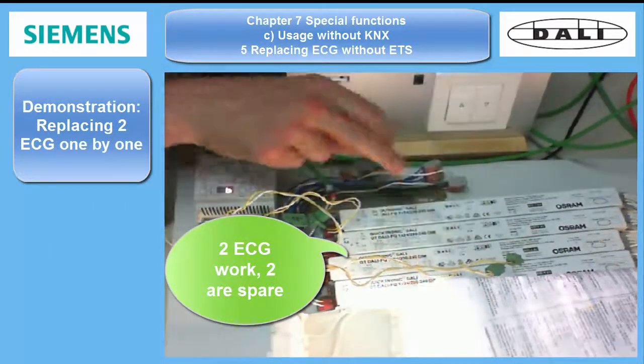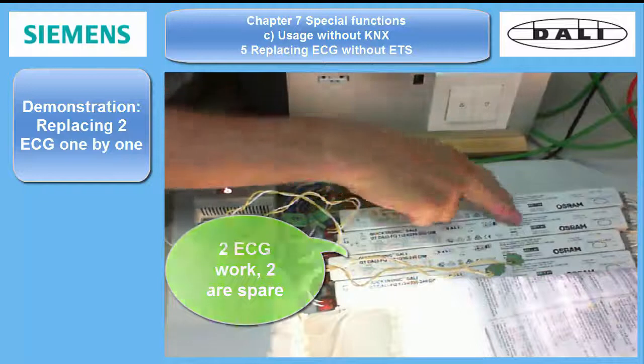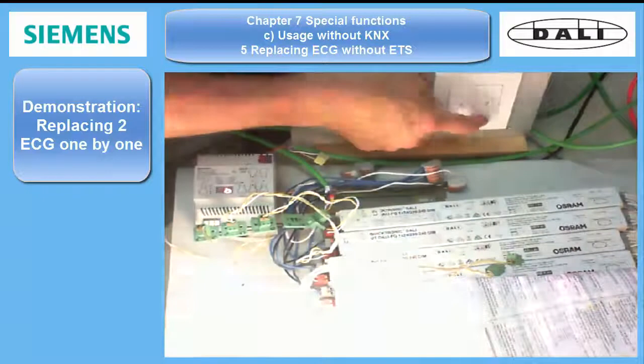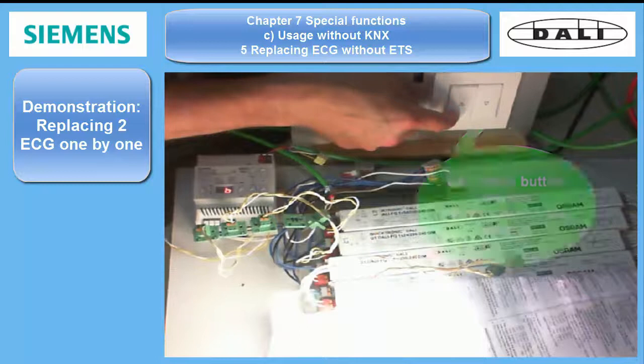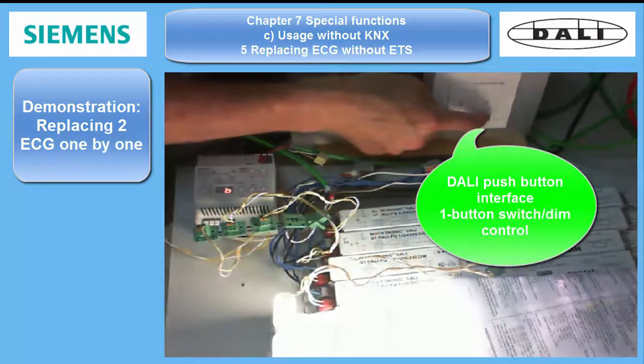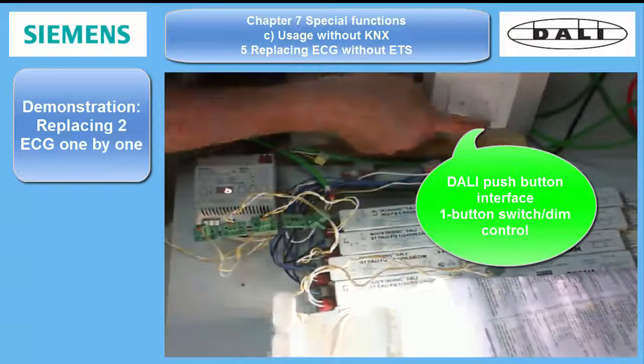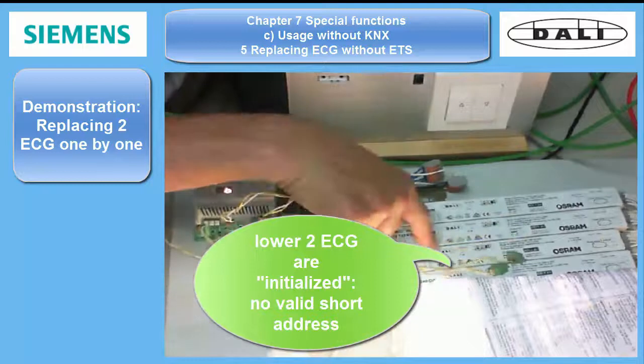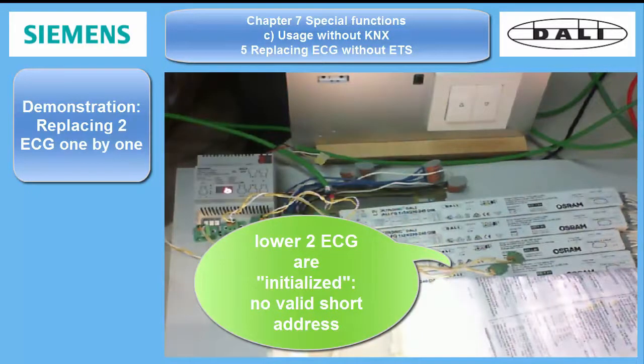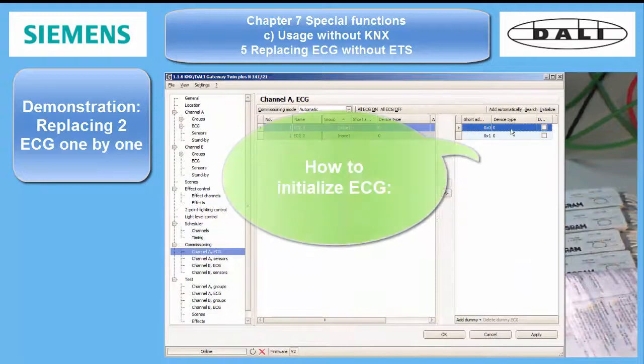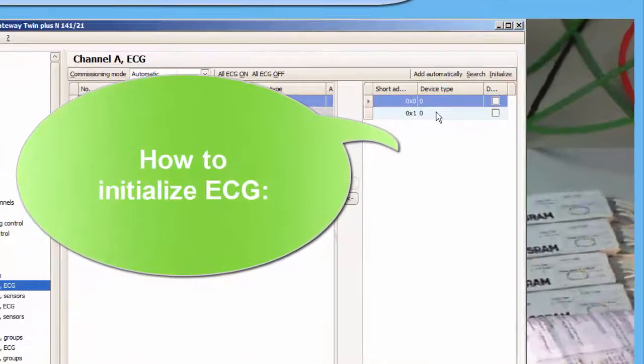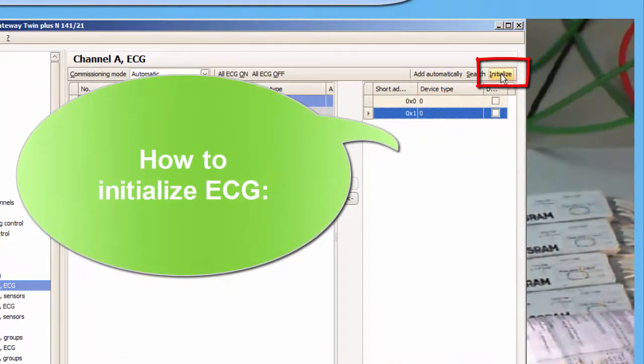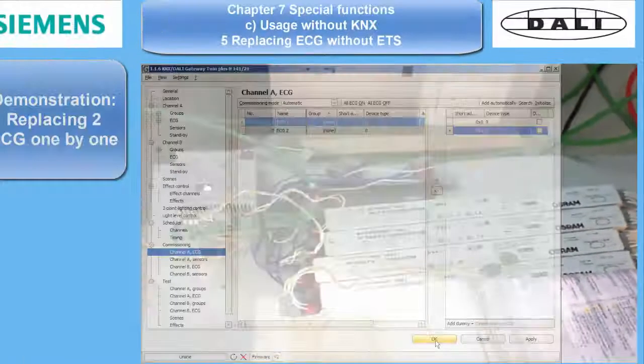I am starting with a configuration of two groups respectively ECG. On this board I have four ECG. The upper two of them are paired with the lower two push buttons on the panel. The buttons work as a one-button dimmer function. The lower two ECG are initialized, meaning they don't have a valid short address. This condition can be achieved in the commissioning dialog of the DALI Gateway after a bus ECG scan. The ECG must be selected and the button Initialize be pressed.